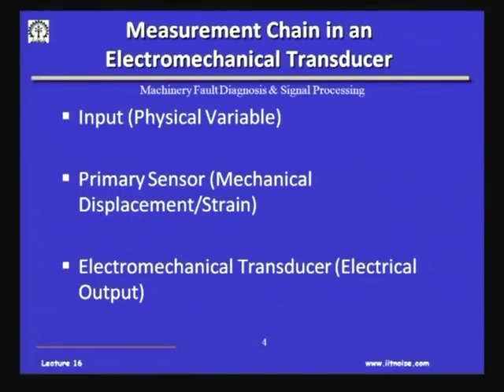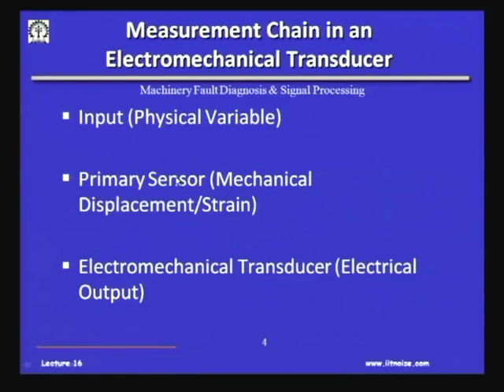Going back to the pressure gauge example, the measurement chain in an electromechanical transducer has three elements. First, the physical variable — load/force in the case of a load cell, or pressure in the case of a pressure gauge. Second, the primary sensor — that mechanical displacement or strain, like the membrane which deflected with a strain gauge on it. Third, the output which corresponds to the characteristic of the sensing element. Everything put together is an electromechanical transducer, which is a superset of the sensing element.